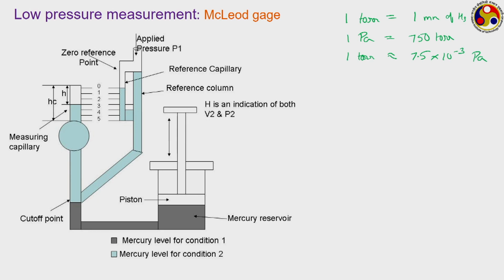One classical instrument for measuring such low pressure levels is this McLeod gauge. Now, look at the configuration that is shown here. Here we have these 2 tubes, almost like a U-tube kind of configuration, but these 2 tubes are connected through this particular line to another big chamber, which is filled with a certain liquid, maybe mercury, and on top of this cylinder we have this kind of piston or plunger arrangement.